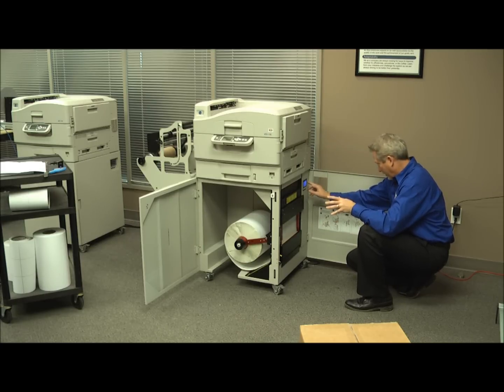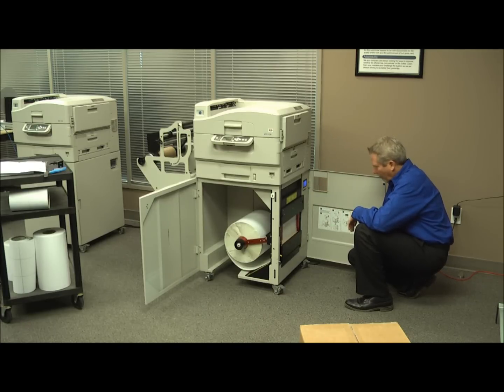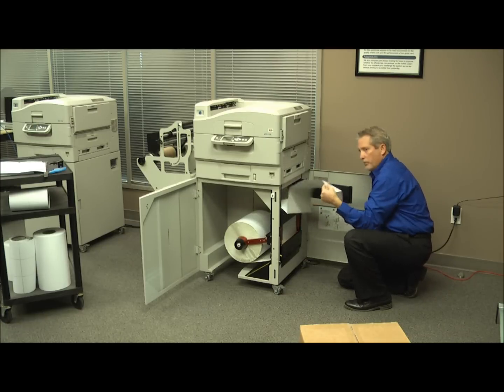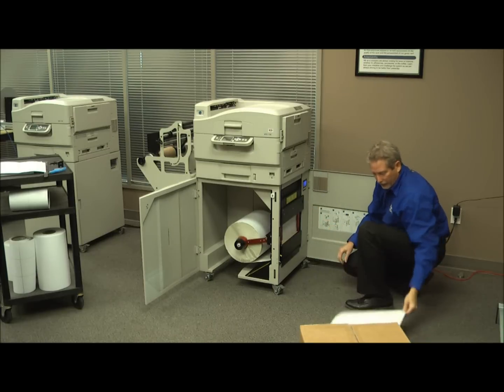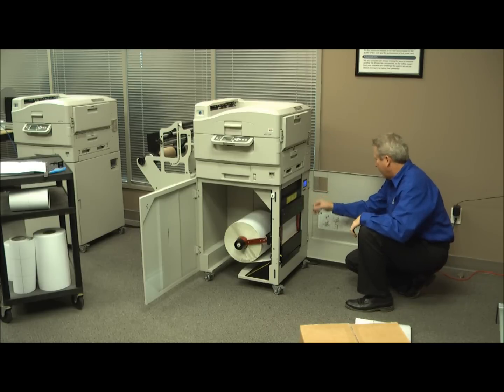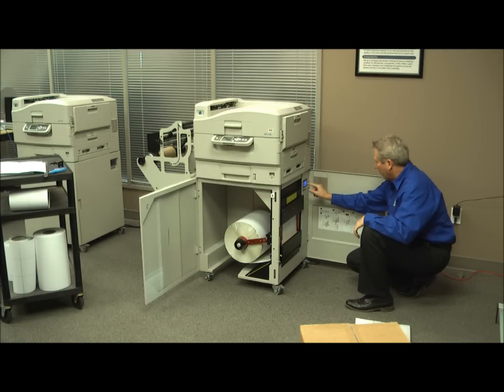So it says on the front panel, it says require load. So let's hit the load button. And then we remove the media. So you'll be removing it from the front. And then we hit done. And we're up to this perfect position for what we get as a loaded message on the front panel. Under status, it says idle. That means everything is fine. We don't have any lights on. We don't have a red light. We're good to go. So now we got to go in and start doing our label setup.